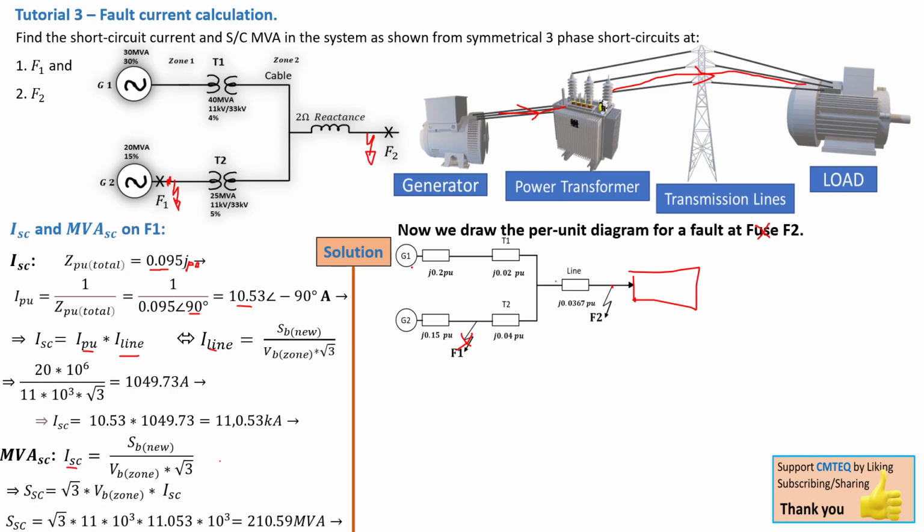But now, how did this current become so big there? Because the generator here is pumping the current coming through this way, through this line, and generator 2 is also doing exactly the same thing through this way and through the line. So automatically you have the current merging on the line and then dropping into this point here and putting your equipment offline. So you then need to calculate your new Z per unit total based on the path the current is going to take.